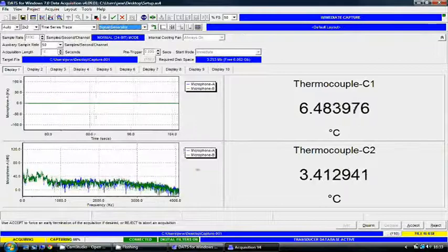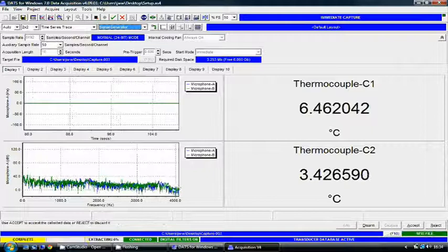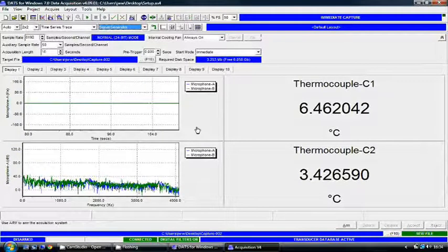We set 10 seconds for the data capture in the previous tutorial, so now we'll capture data for 10 seconds, and at the end the data is saved and the P8000 disarms itself. So we're now ready to begin with the process of analyzing the data.